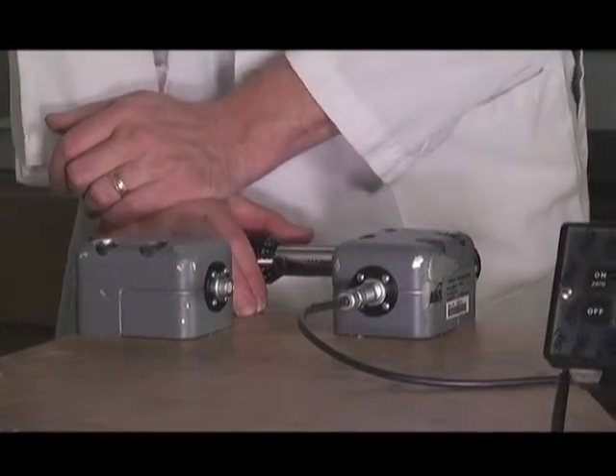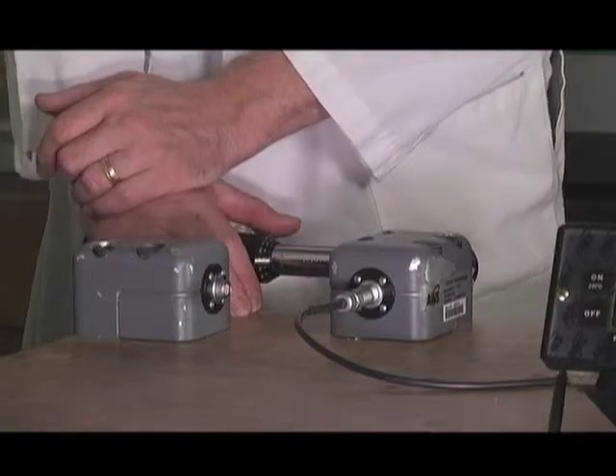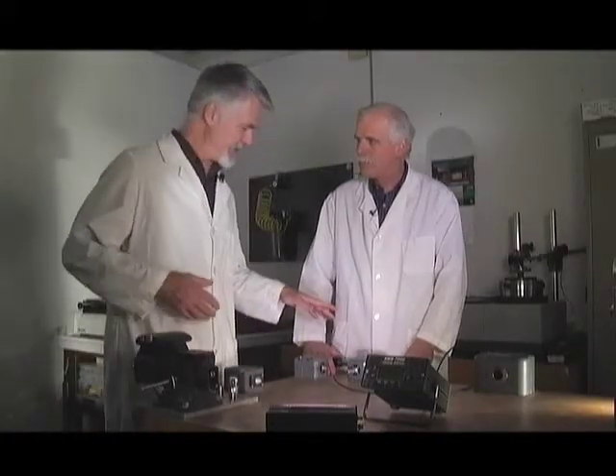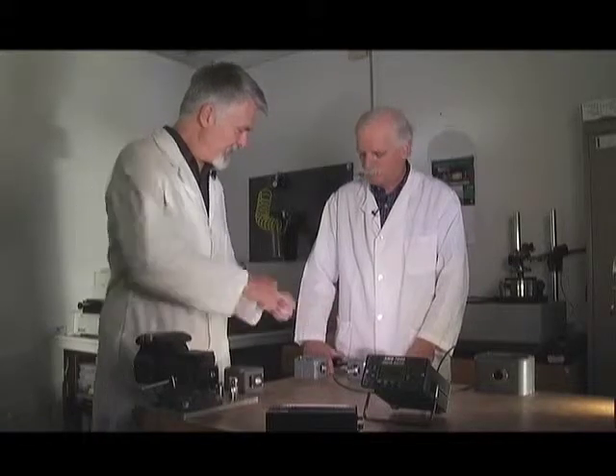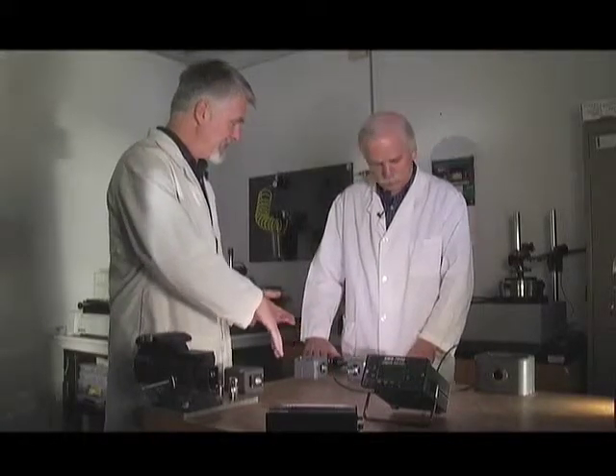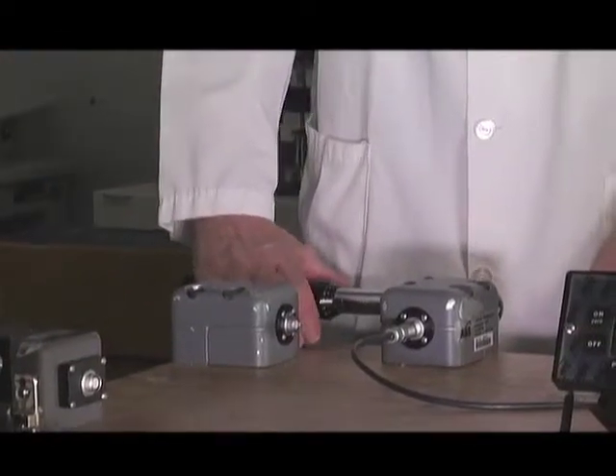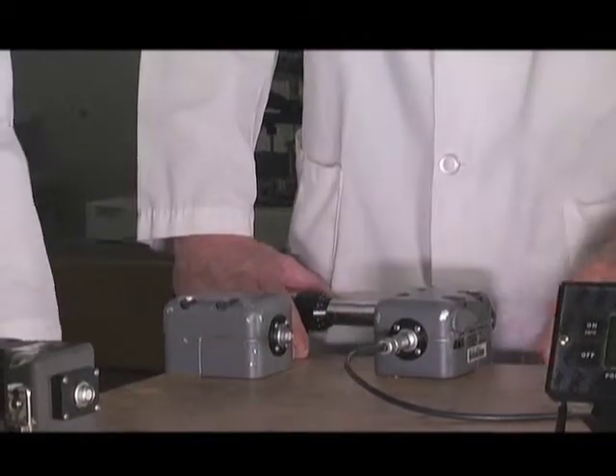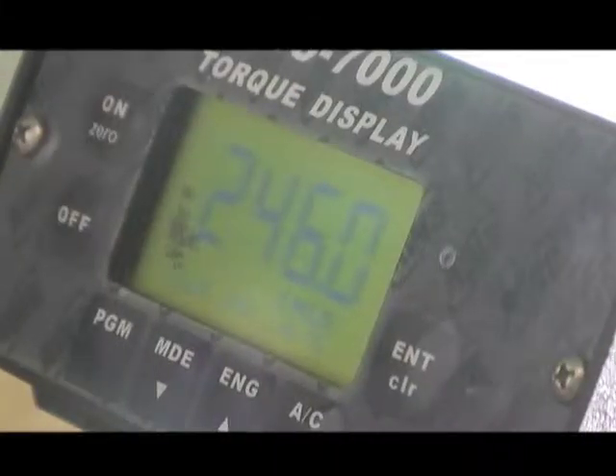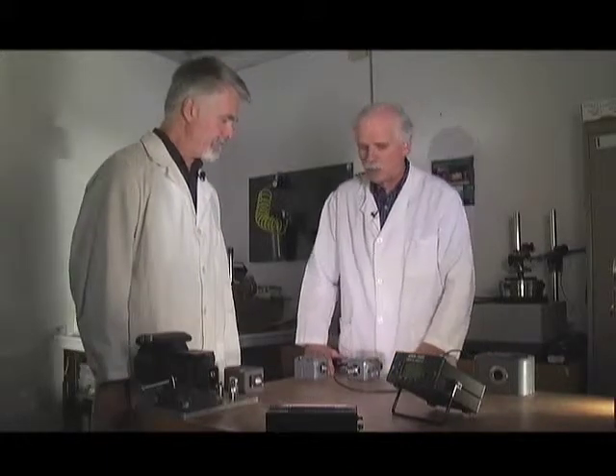Usually our standard says to give it 5 clicks before we take our reading. Okay. Let me step back, I'm a little confused about what's actually happening. So that little click, that means it thinks it's reached its torque. It has. Yes. You've reached 250. If you watch the display, you'll see it. 246. Yeah. It's set at 250 with the tolerance. It can go from 240 to 260. Okay. So it's reading well within the range.